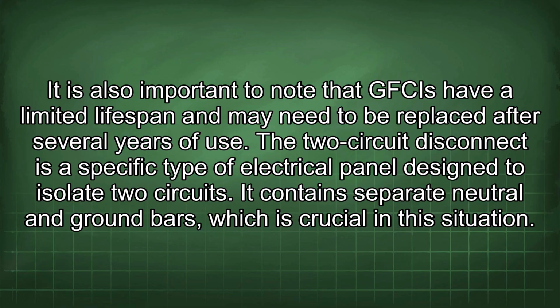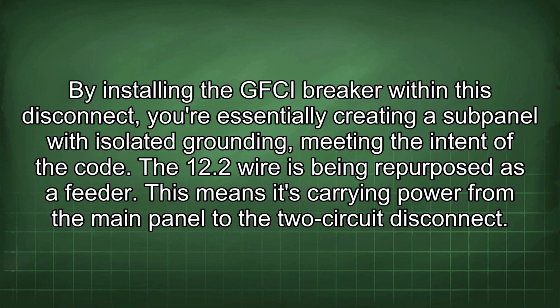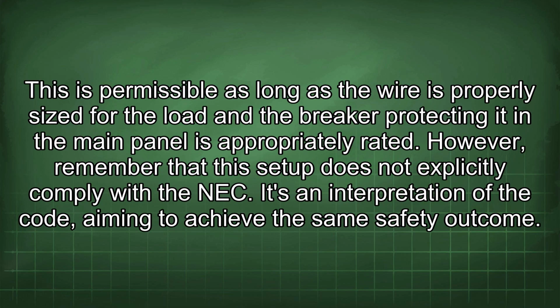The two-circuit disconnect is a specific type of electrical panel designed to isolate two circuits. It contains separate neutral and ground bars, which is crucial in this situation. By installing the GFCI breaker within this disconnect, you're essentially creating a subpanel with isolated grounding, meeting the intent of the code. The 12/2 wire is being repurposed as a feeder. This means it's carrying power from the main panel to the two-circuit disconnect. This is permissible as long as the wire is properly sized for the load and the breaker protecting it in the main panel is appropriately rated.